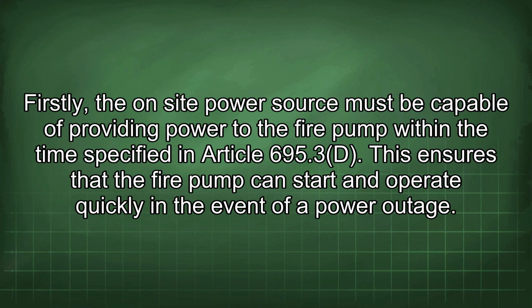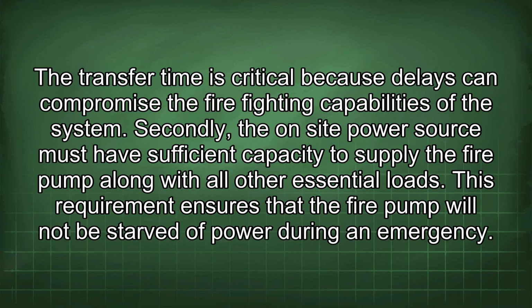Firstly, the on-site power source must be capable of providing power to the fire pump within the time specified in Article 695.3d. This ensures that the fire pump can start and operate quickly in the event of a power outage. The transfer time is critical because delays can compromise the firefighting capabilities of the system.